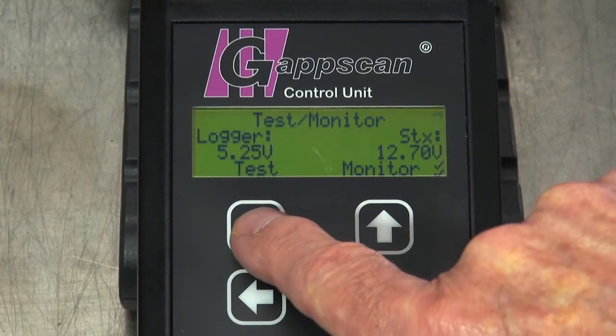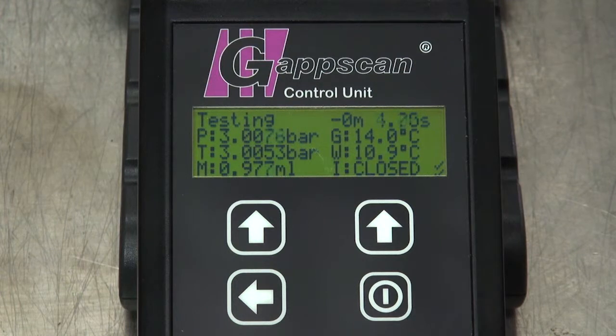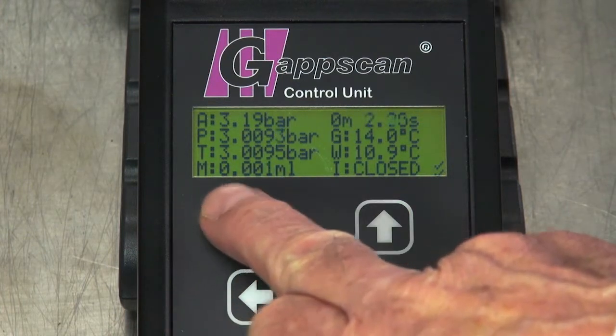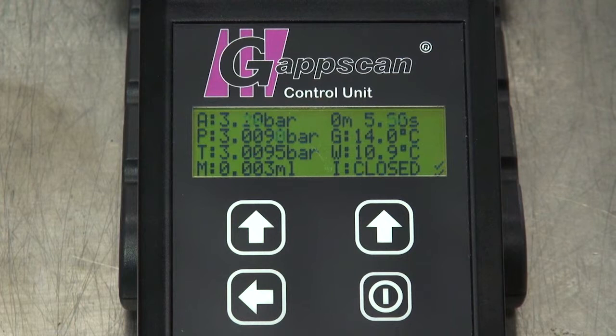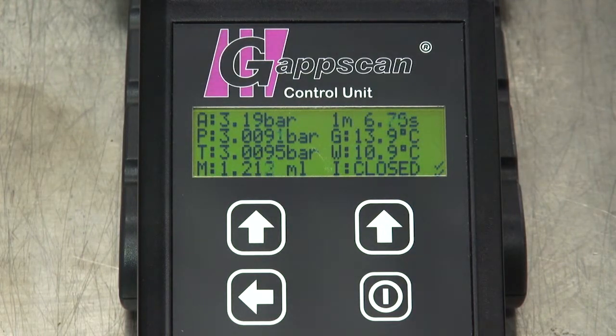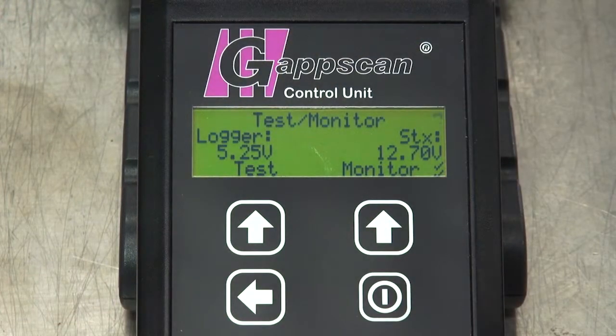Press the return key, then select Test from the menu. When Test is selected, an automatic sequence begins. The test will complete when either the measurement has reached a loss of fluid of approximately 18 millilitres or the test period of 5 minutes has elapsed. The test time will be seen incrementing in real time. To abort a test during test mode, press all 3 arrow keys at the same time to return to the test monitor screen.